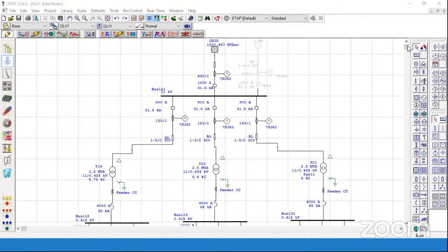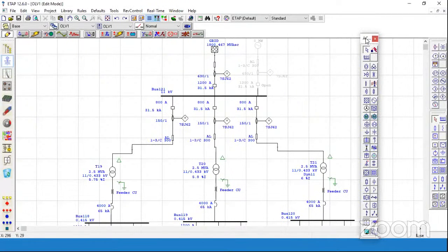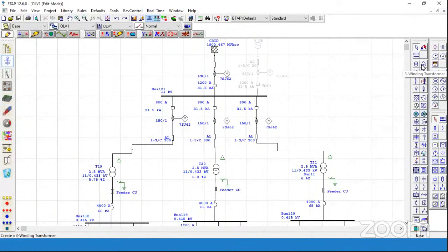With ETAP, there are certain elements listed here in the component library, like bus, transformers, three winding transformers, cables, transmission line, reactors, certain branches, grid, power from the grid, generators, PV array, where PV means photovoltaic module, wind turbine generators, and motors. Likewise, there are many components helpful to evaluate studies in ETAP. What we need are the equipment details used in our electrical system, as well as for measurement the CT and PT details, and circuit breaker details in terms of protection. All these details we require to perform these studies.